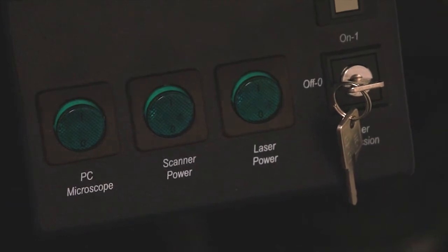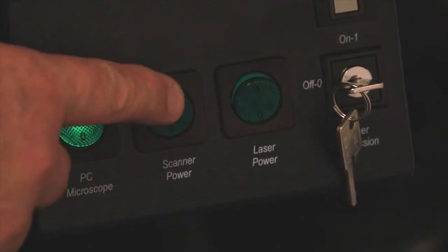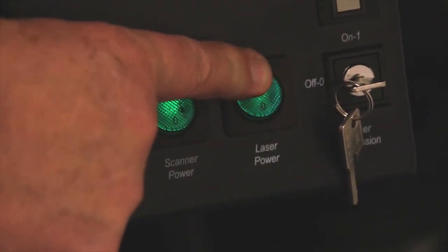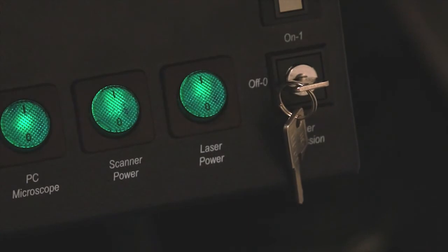We will begin again with an overview of the confocal microscope, the Leica SP, and then we will delve into more specifics about individual components of the microscope. To initialize the confocal microscope, you must first apply power to the microscope and to the computer which drives the software. You also would apply power to the lasers, but we will hold off on that until another segment.